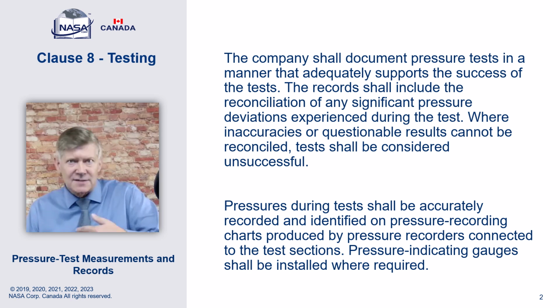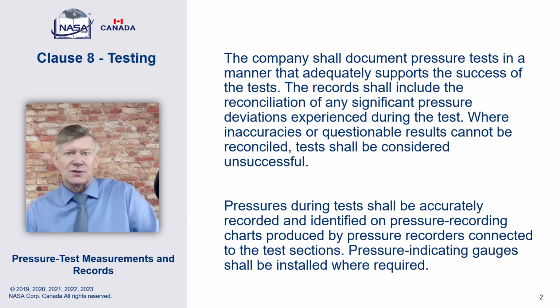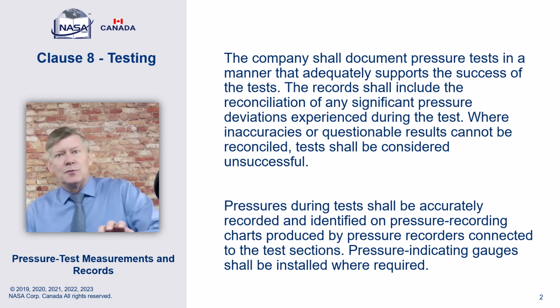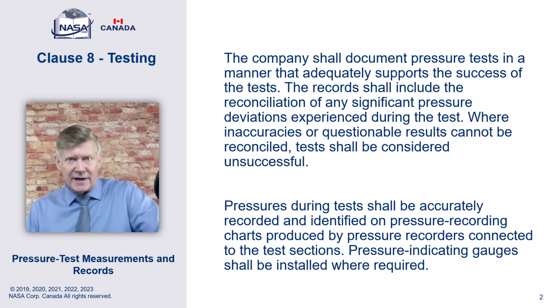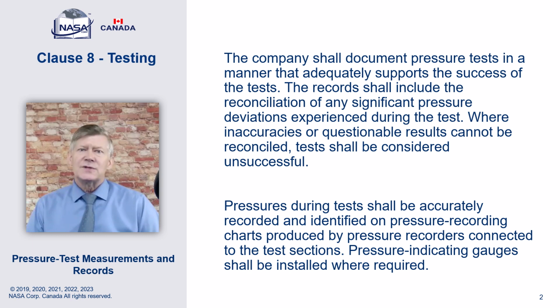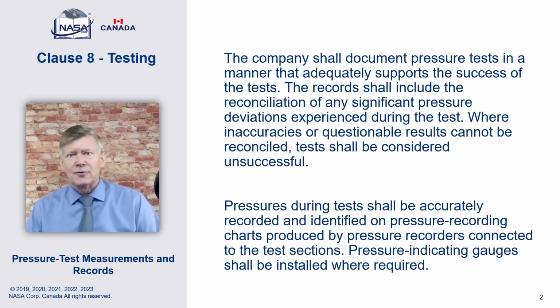And that's, again, it's from that experience that my recommendation is that if you can see a deviation on the plot, you'd better be able to explain where it's from. Right? 8772 says pressures during tests shall be accurately recorded and identified on pressure recording charts produced by pressure recorders connected to the test sections. Pressure indicating gauges shall be installed where required.